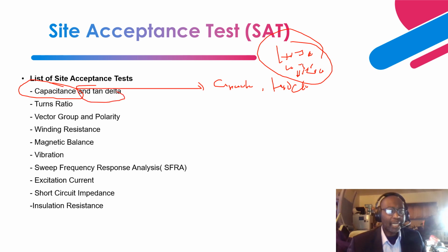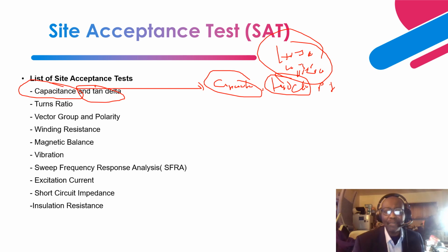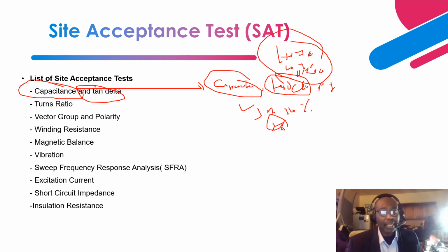So we perform what they call AC diagnosis testing, right? We perform the testing of this capacitance and the tan delta, that is power factor. With the power factor, we are determining the contamination level of both the solid paper, thermally upgraded paper, and the oil in the transformer. So we compare the testing results with the nameplate data, especially the capacitance, or the factory acceptance testing results, to determine if there's any delta. If you have a delta greater than 10%, then that should be a concern that you have to investigate. A delta shouldn't be greater than 5%. 5% is the criteria for a change in capacitance. So if you have results that show a capacitance change greater than 10%, then there are other tests you have to do to confirm that indeed you have a change in the geometry of the active component. The active component is the core and coil of the transformer, including the clamping structures.